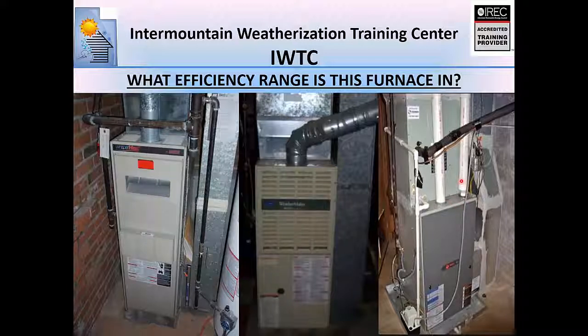The way this one is installed, because it's a direct vent appliance with 2 pipes, there is no chance of backdrafting this into the envelope. But these 2 guys over here, they can backdraft, including this one. Okay, it takes a lot to get this guy to backdraft, but it can happen. So this one and this one should both be tested under worst case conditions. This one's a direct vent, don't need to worry about it. So the one in the middle must be tested because of those combustion air louvers, right? Because if the CAZ was really negative, it could actually draw air back out of the flue. Is that correct? Absolutely. Yep. It can actually pull air back out.